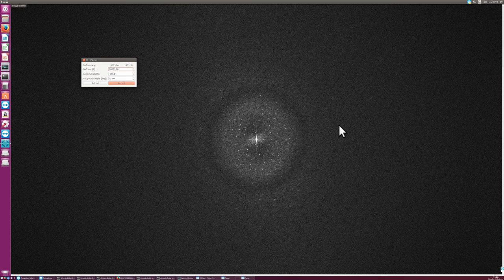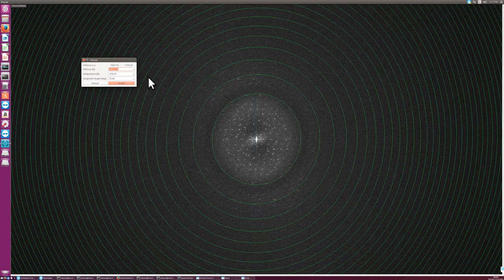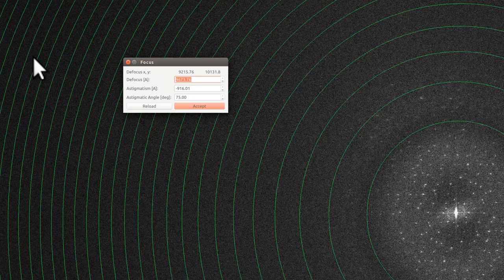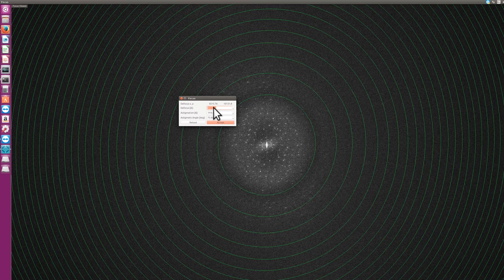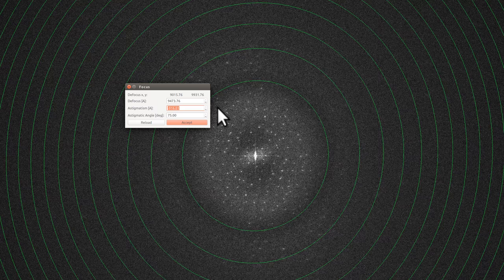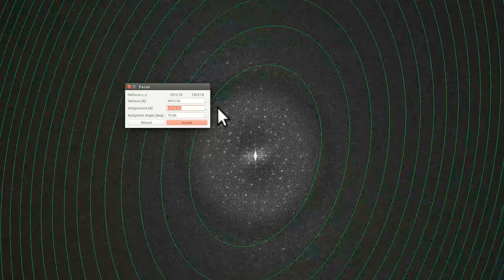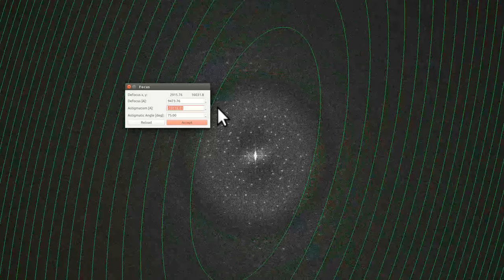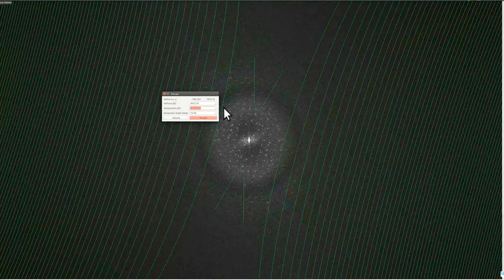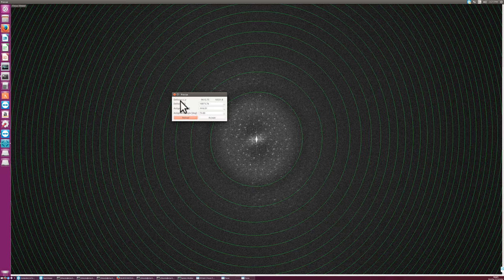So, let me verify if this is correct by just displaying the thon rings here. With N, I make this darker. And with C, I can display the thon rings here. Letter C, and this looks good. I can, with C, click this on and off. This looks good. Otherwise, I could move the thon rings with cursor up and down or page up and down on the keyboard. Or I can modify these values here by hand if I want to. These lines are for astigmatism. These are zero crossings of the simulated CTF. If I set the astigmatism, for example, to something very extreme, then it becomes elliptic. And then later on, these become hyperbolas, as astigmatism should be.